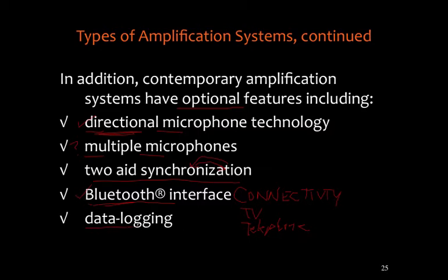Data logging, since these hearing aids are computers, after all. Now we can keep a record of what the hearing aid is doing, and particularly if a person is using multiple memories, under what conditions they are using them. We can look at how many times the hearing aids went into compression, and monitor whether or not the person is getting optimal amplification.